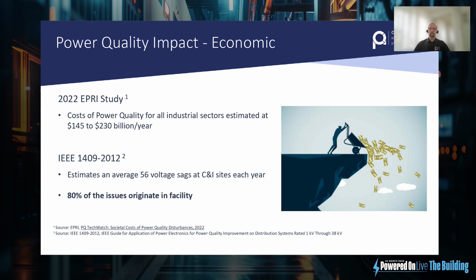What's the impact? Globally, it's a massive problem. As you can see there, an estimated 230 billion dollars a year is lost to power quality related issues in industry as a whole. What often gets overlooked is that over 80% of those problems are usually caused within the facilities of the equipment we're talking about. They're not coming from the grid; usually less than 20% of issues come from there. One of the main reasons is that the hardware being installed is getting more and more complicated, and we'll talk about that in a second.